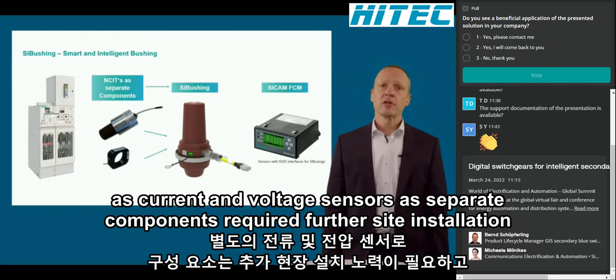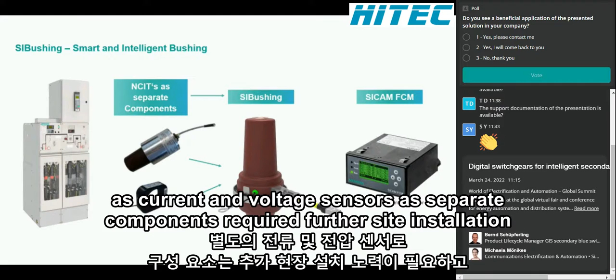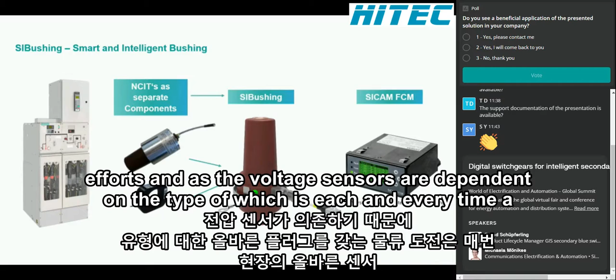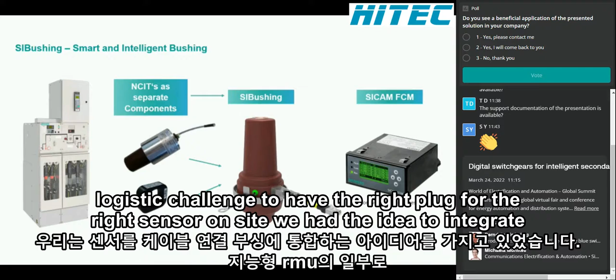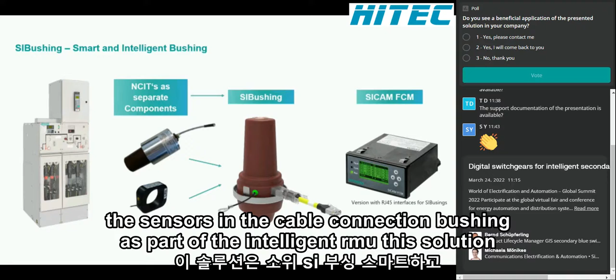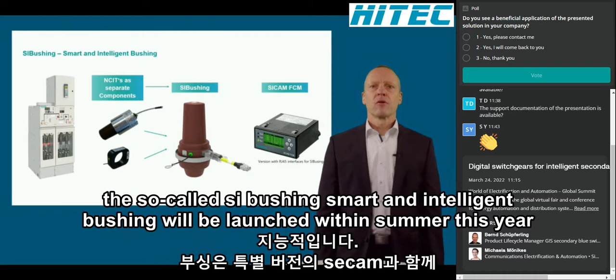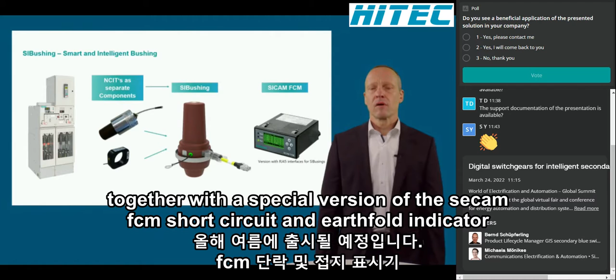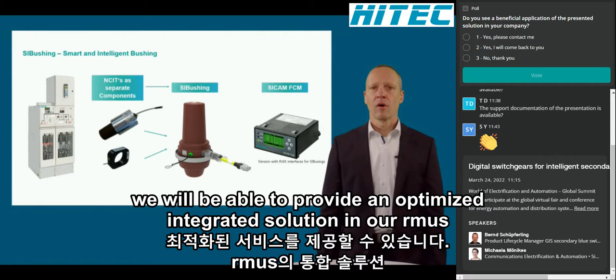As current and voltage sensors are separate components that require further site installation efforts, and as the voltage sensors depend on the type of T-plug, which is each and every time a logistic challenge, to have the right plug for the right sensor on site, we had the idea to integrate the sensors in the cable connection bushing as part of the intelligent RMU. This solution, the so-called SI bushing, Smart and Intelligent Bushing, will be launched this summer. Together with a special version of the SICAM FCM short circuit and earth fault indicator, we will be able to provide an optimized integrated solution in our RMUs.